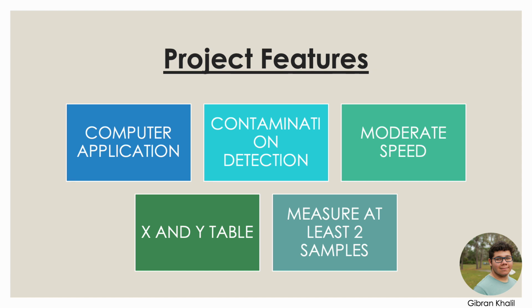We want it to have moderate speed, so that it goes through the samples fairly quickly, given a 10-15 second time per sample. The X and Y table allows us to do the measurements of at least two samples at once. It just moves the table with the specific sample and allows us to measure them one after another.